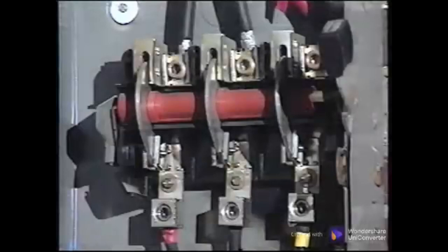Depending on the type of panel, there may be large lug connections, fuses, breakers, or a throw switch. When connections of any type are loose, heat is generated because loose connections cause electricity to jump or arc across the joint. Arcing heats the joint and can cause pitting. Another reason for the excessive heat is that the loose connection acts similar to a wire or cable that is sized too small for the load. It is attempting to carry more electricity than the touching surfaces can allow. Excessive heat is generated when a lug is not tight on the wire, or a fuse is not tight in the holder or any other connection.